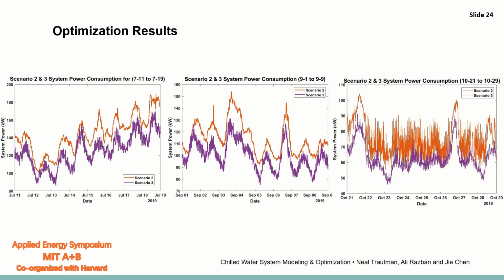This slide compares scenario 2 and 3. So this is the baseline versus just an optimized cooling tower fan. As you can see, scenario 3 was consistently more efficient than the baseline from July all the way to October, excuse me. This would indicate that there is potential to save energy through optimizing the cooling tower fan.